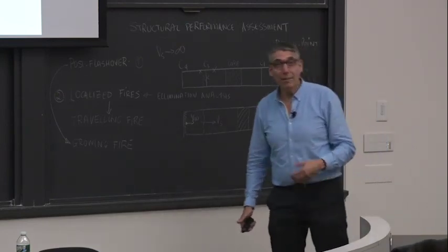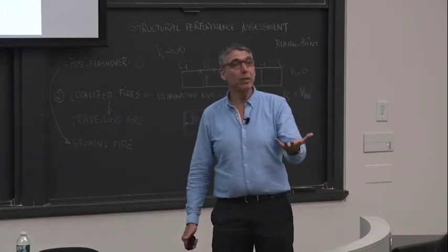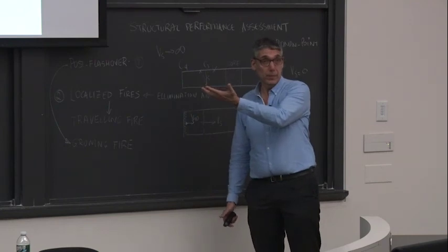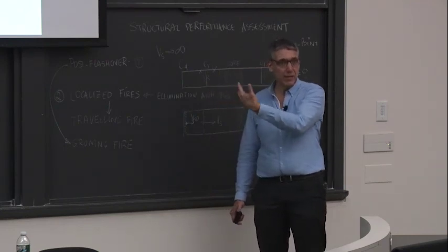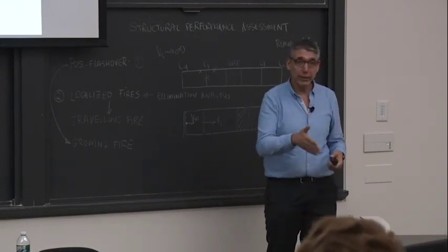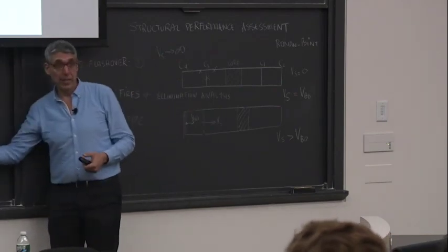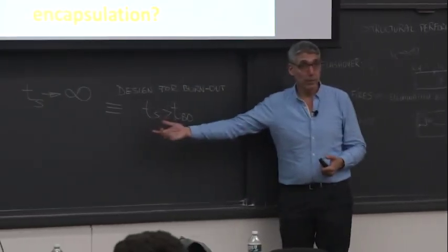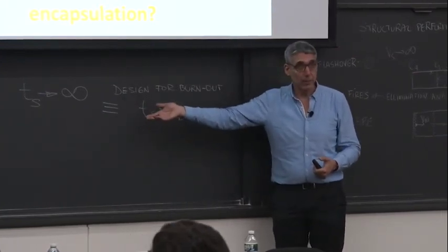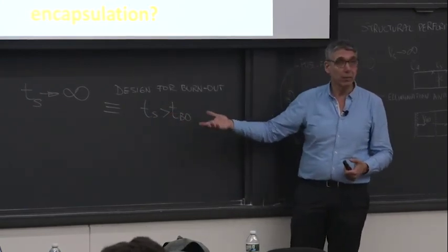I mean, you think this is funny? The timber industry spends millions promoting the success of the fire resistance tests without recognizing that it's met all the failure criteria, but it hasn't met the fundamental principle that enables a test. If this thing is going to continue to burn, it will collapse. And therefore, it doesn't meet the criteria of design for burnout.